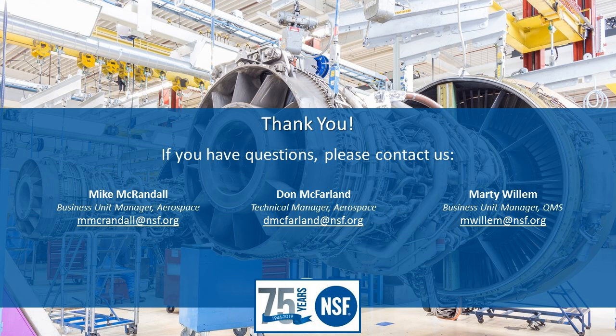Could I add something to that, Don? Of course. In a tool room environment, it would behoove you to have calibrated gauges that you can rely on, because of the tool steel and everything that goes into it, and the time and the effort with the highly skilled resources, only to find out that the tool was no good when you do your first article or make your first production piece, and then try to find out what the root cause of the failure was, is going to be excessively expensive compared to probably having the calibrated gauges.